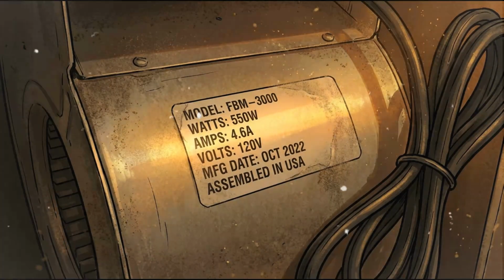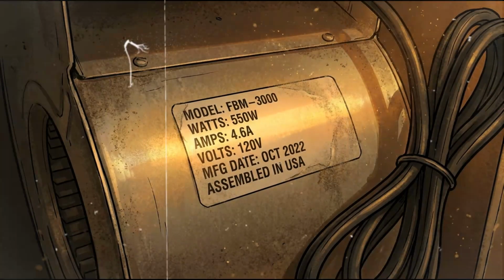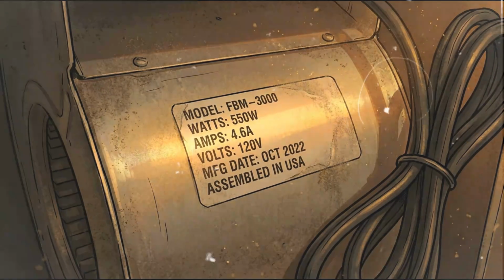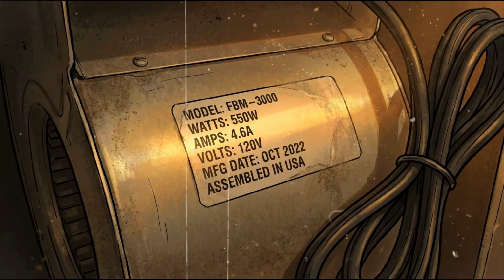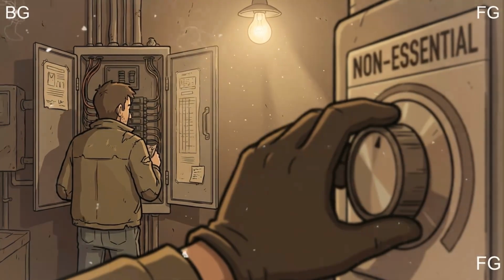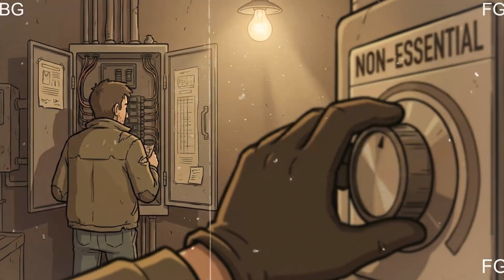Refrigerator: 100 to 400 watts running, 1500 watts startup surge. Furnace blower: 300 to 800 watts. Basic LED lighting, 3 rooms, 30 to 60 watts. Phone charging, 2 phones, 20 to 30 watts. Medical devices, if applicable, varies widely.